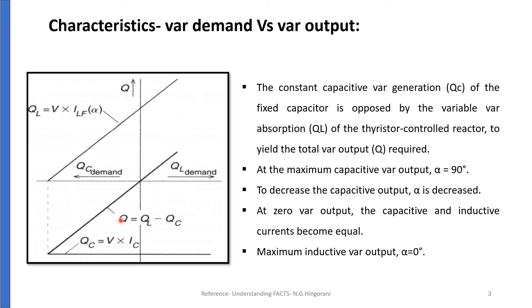We vary QL by varying alpha because the fundamental current of TCR is an alpha-dependent quantity. At the maximum capacitive VAR output, the thyristor controlled reactor is off, i.e. alpha is equal to 90 degrees. At zero VAR output, the capacitive and inductive currents become equal and thus the capacitive and inductive VARs cancel out each other. With further decrease in angle alpha, the inductive current becomes greater than the capacitive current, resulting in a net inductive VAR output. This is possible only when the rating of the reactor is greater than that of the capacitor.